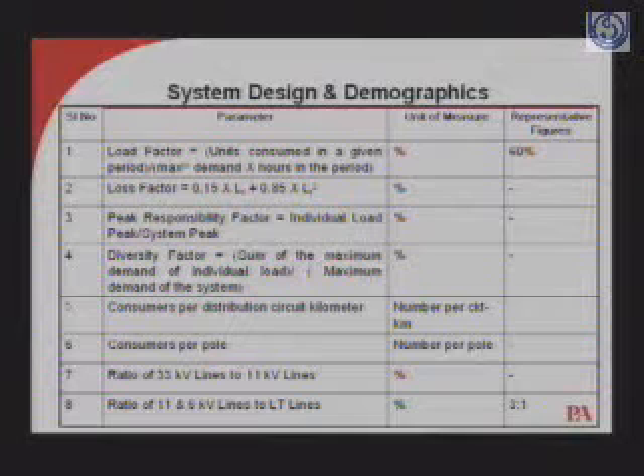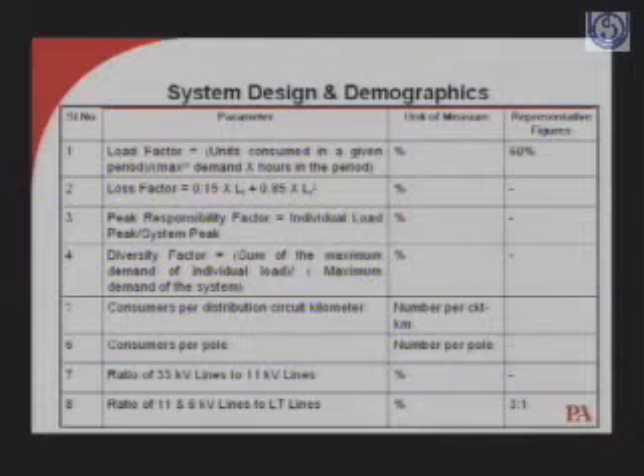For example, system design and demographics. What is that? You all know there is something called load factor. Load factor will give us an indication of how much energy will be consumed. So load factor means average by peak, the way it has been defined: units consumed in a given period divided by maximum demand into hours in the period. Some organizations, or all organizations should, do it on a month-wise as well as year-wise basis. Month-wise load factor and year-wise load factor will differ. There is no doubt about it.